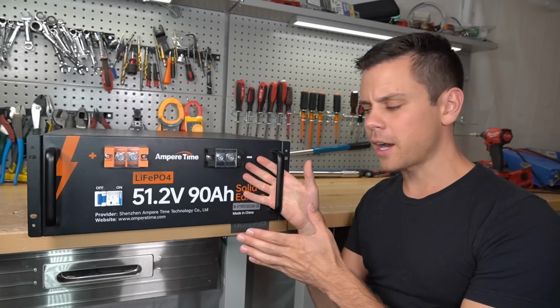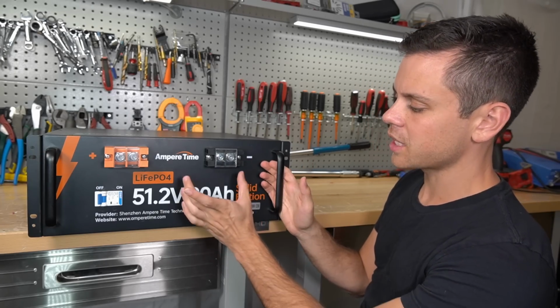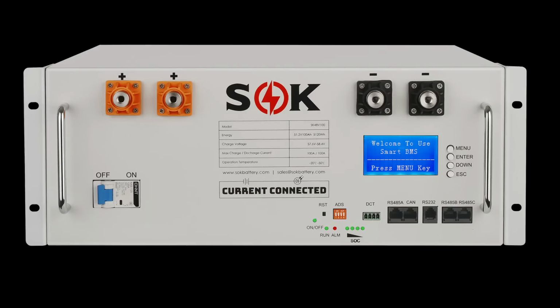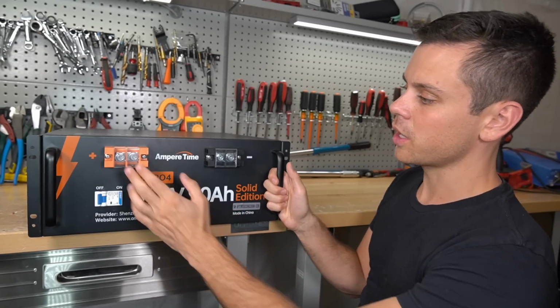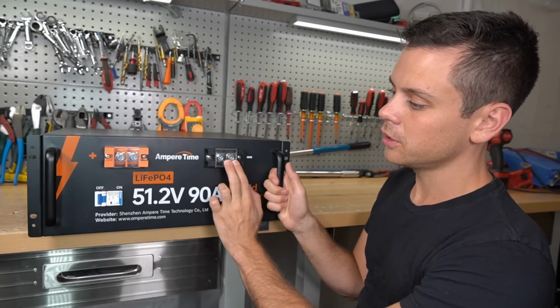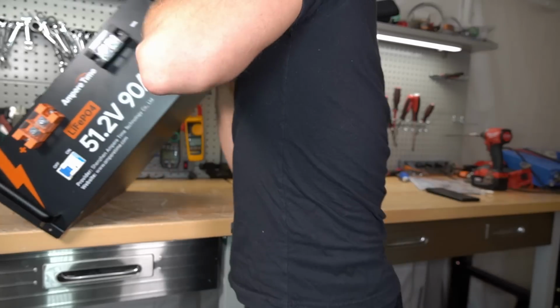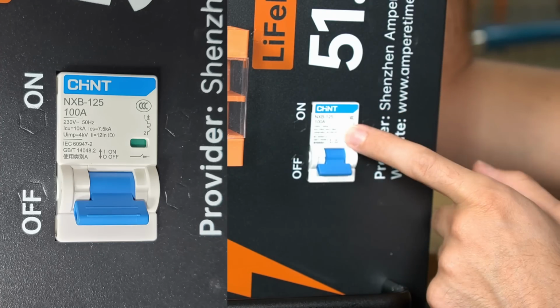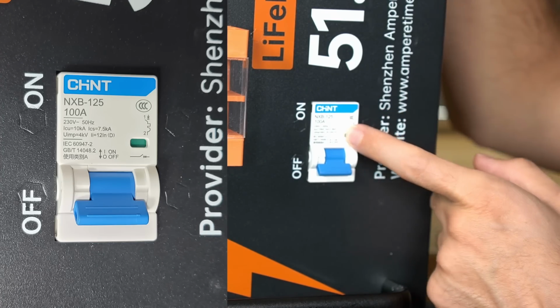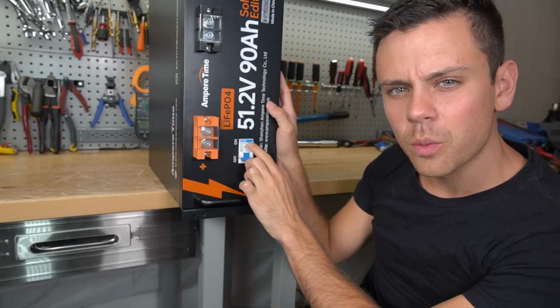Next, other server rack batteries on the market have communication ports, they have a screen, state of charge indicator, lots of cool features on the front. This one is bare bones. We have a positive terminal, a negative terminal, and a circuit breaker. And unfortunately, this is not a DC rated circuit breaker. That's a big bummer. And it's rated for only 100 amps.